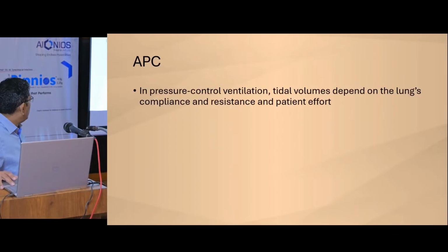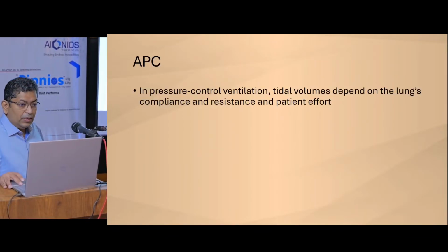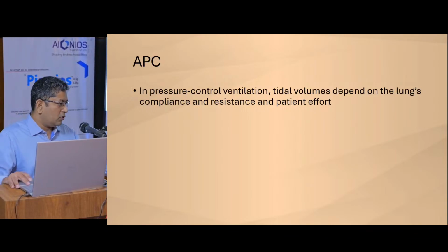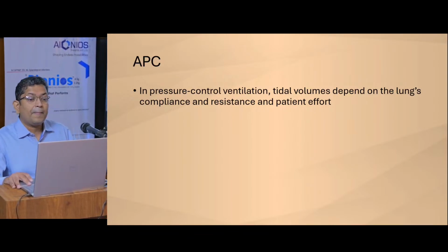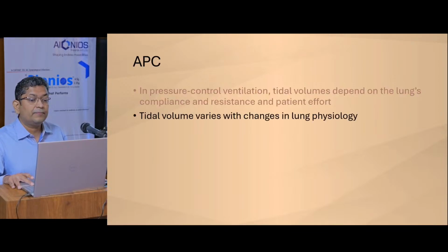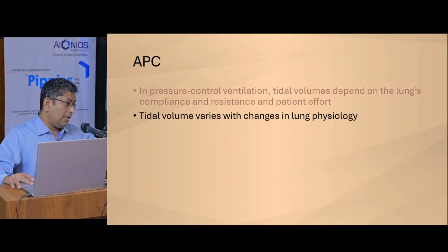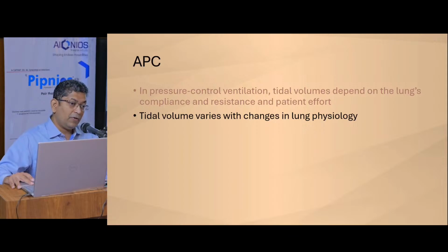Now, what is this? Adaptive pressure control, or PRVC. It's a pressure control ventilation. This is also pressure controlled. Okay. And the tidal volume depends on the lung. In a pressure control, the tidal volume depends on the compliance. Okay, fine. And the patient's effort. So if the compliance comes down, tidal volume comes down. If the patient takes a bigger effort, the tidal volume will go up in a pressure control ventilation, right? Okay, fine.